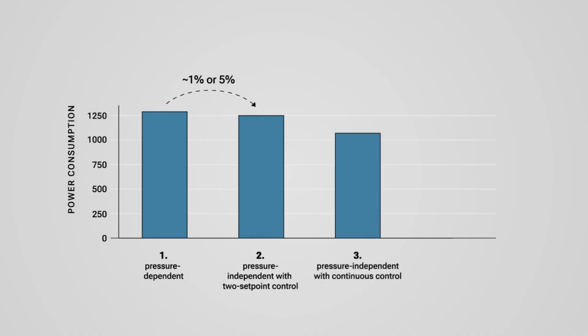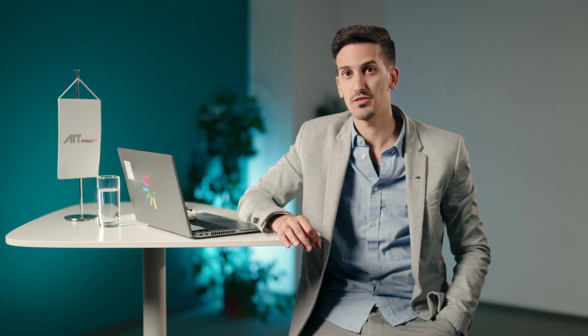Replacing the 2 set-point control with a continuous control results in a reduction of the pump energy consumption of 15%. This is quite remarkable, as there are still many valves with 2 set-point control on the market.